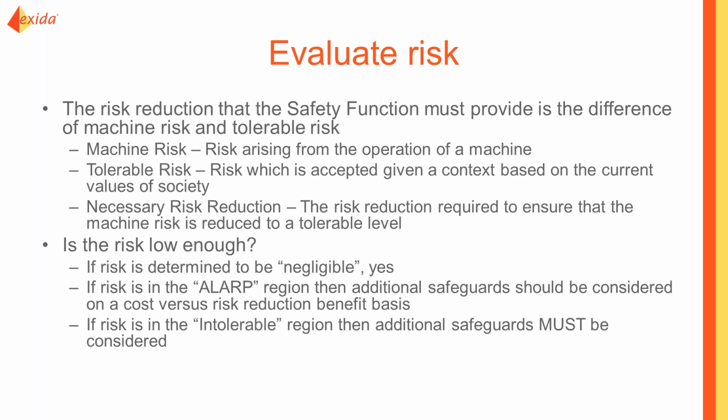So how do you know if you get the risk low enough? It's low enough if it can be determined to be negligible. If the risk is in the as low as reasonably practicable range, then additional safeguards should be considered.